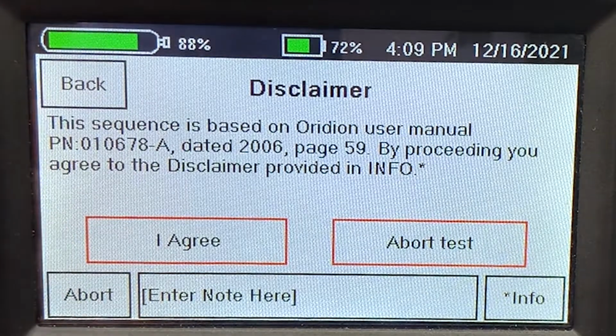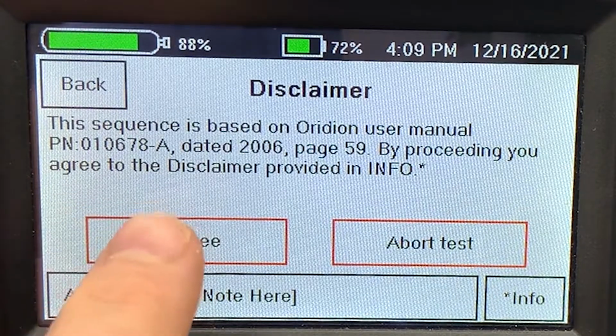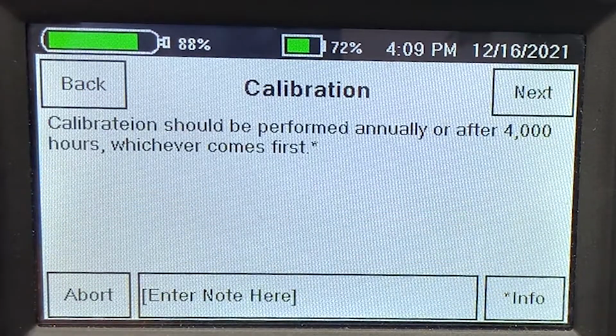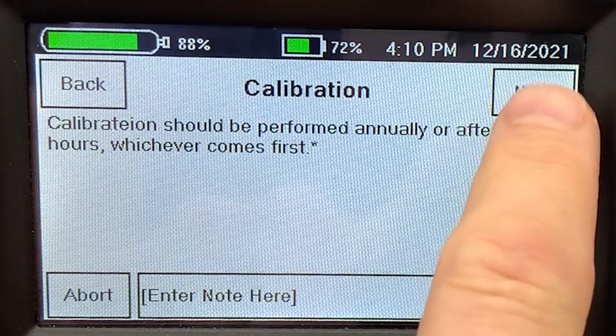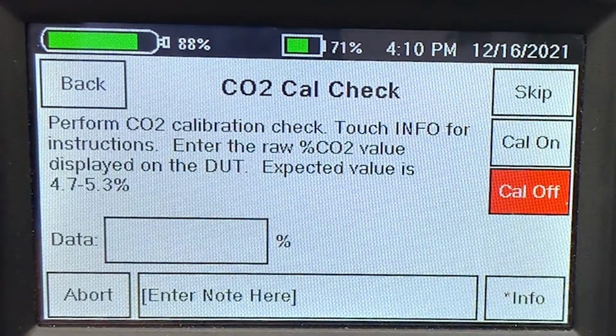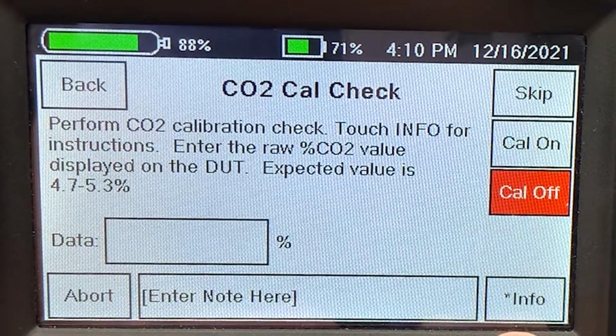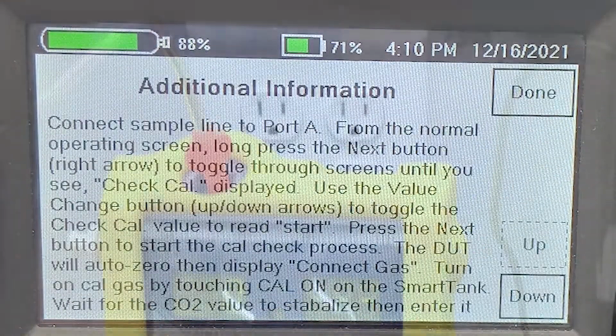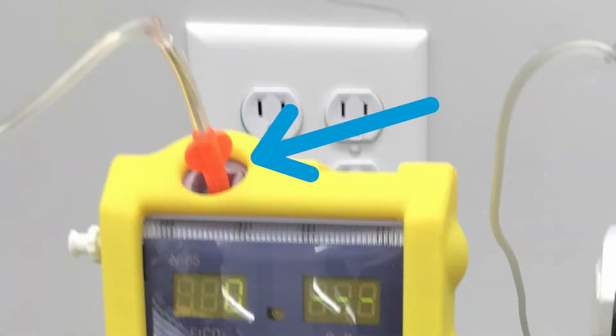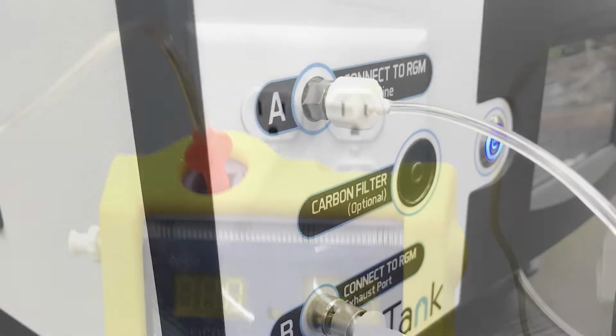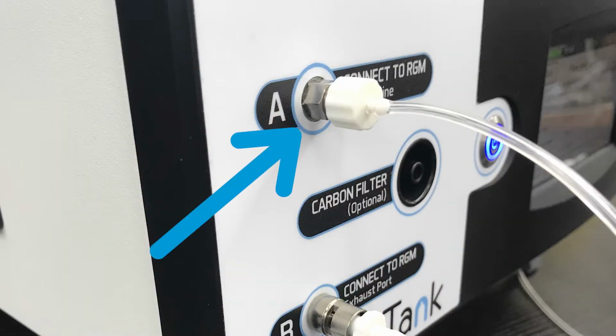I agree means that it's our responsibility to make sure this is the right service routine for this monitor. This screen tells us that calibration should be performed annually or after every 4,000 hours. If we touch here, it'll tell us how to get in and see the number of monitoring hours. So we're first going to perform a cal check. If you don't know how to do that, you can touch the info button. It'll show us how to do it. Connect the sample line of the gas monitor to port A on the smart tank.